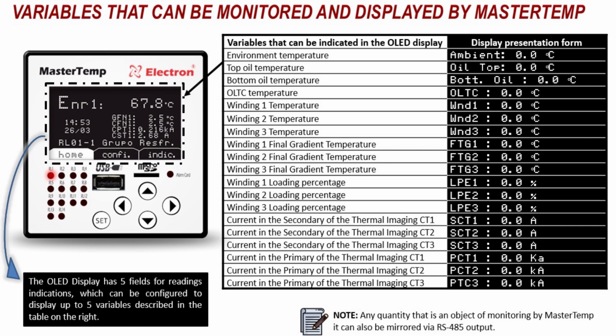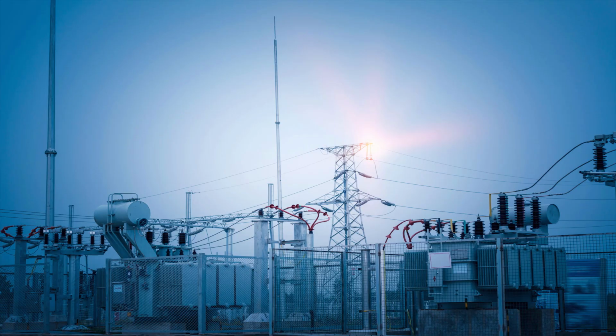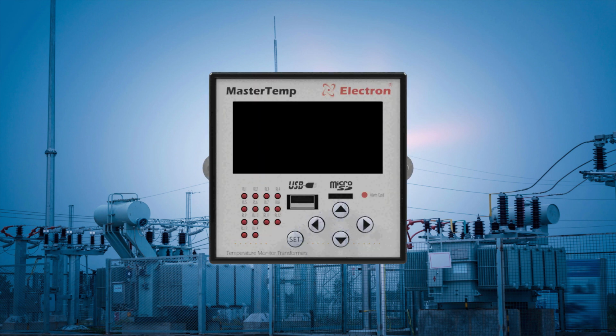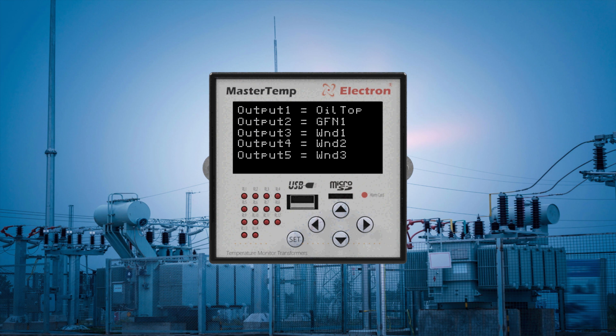Mastertemp also has 5 analog outputs that allow you to mirror any of the magnitudes monitored by Mastertemp. As for example, analog output 1, equal to the temperature of the top of the oil. Analog output 2, equal to the elevation of temperature gradient 1. Analog output 3, equal to the temperature of the winding 1. Analog output 4, equal to the temperature of the winding 2. Analog output 5, equal to the temperature of the winding 3.